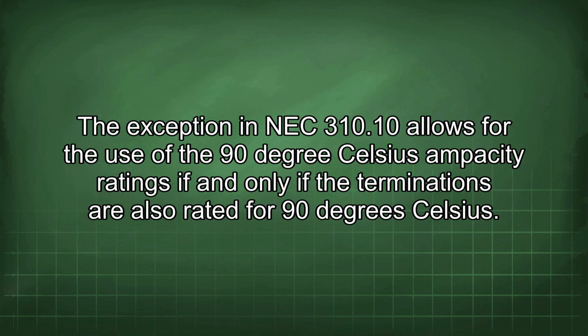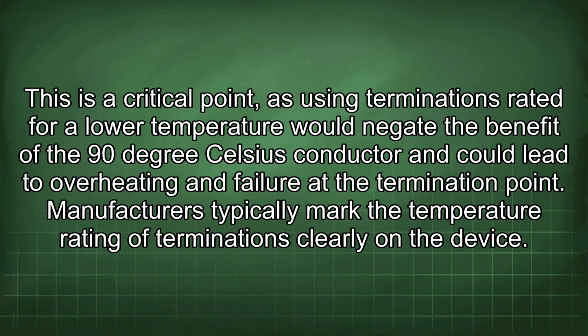tasks. The exception in NEC 310.10 allows for the use of the 90°C ampacity ratings if and only if the terminations are also rated for 90°C. This is a critical point, as using terminations rated for a lower temperature would negate the benefit of the 90°C conductor and could lead to overheating and failure at the termination point.